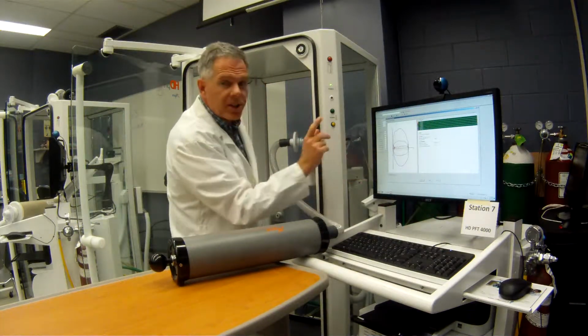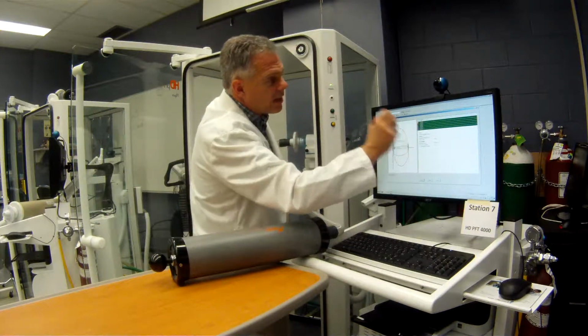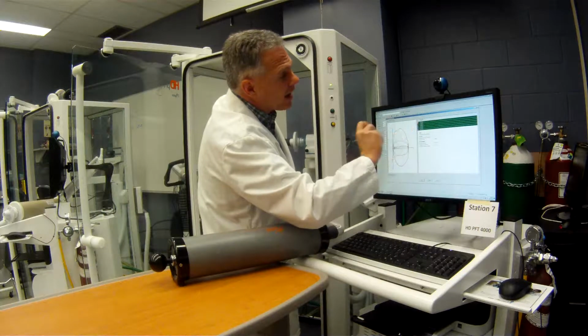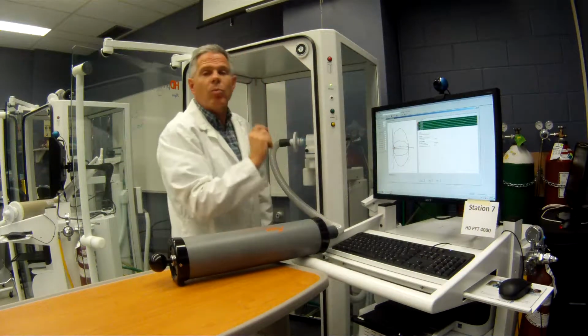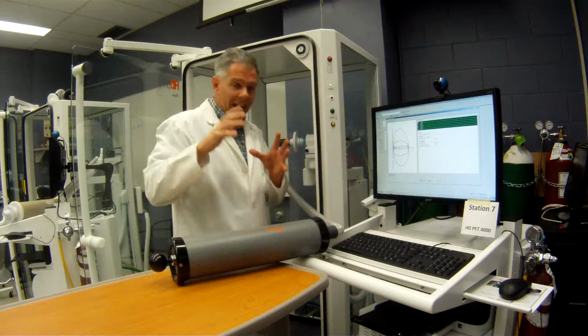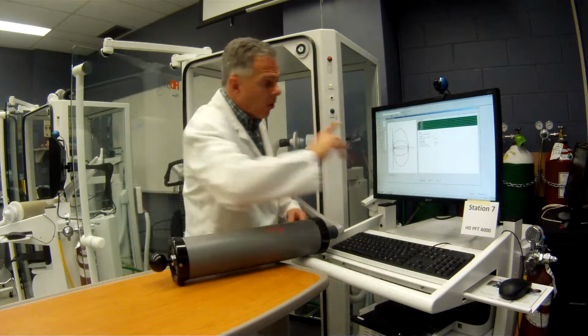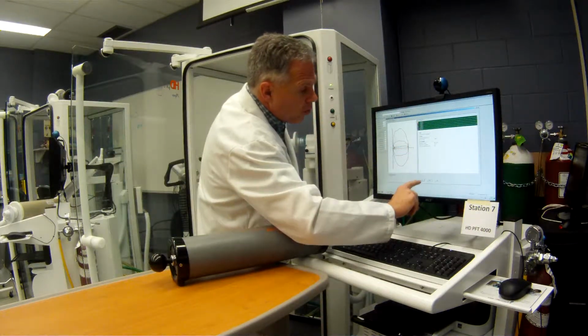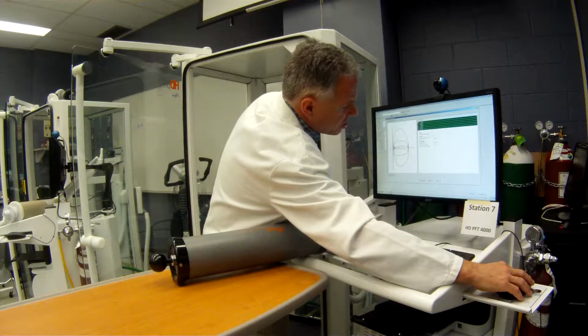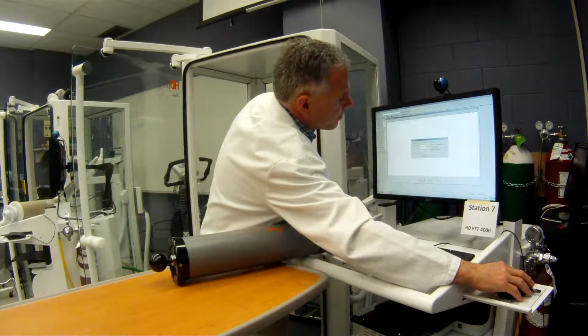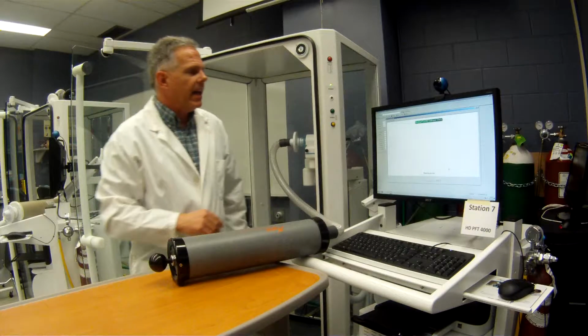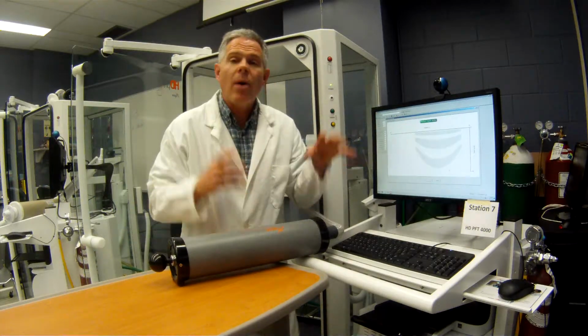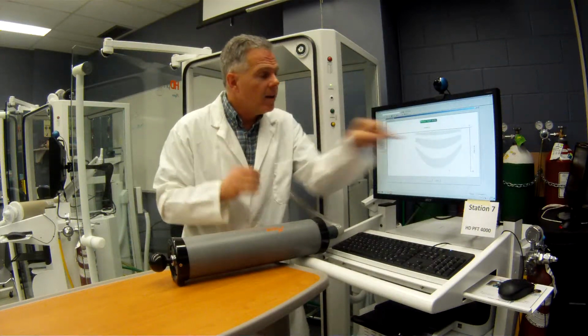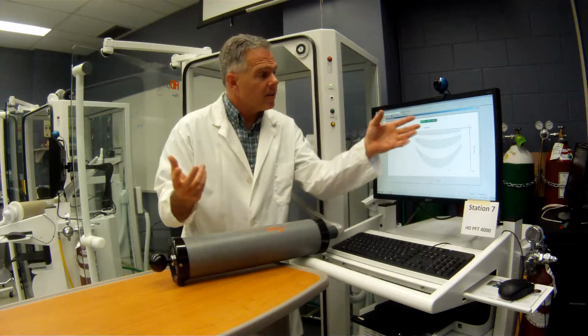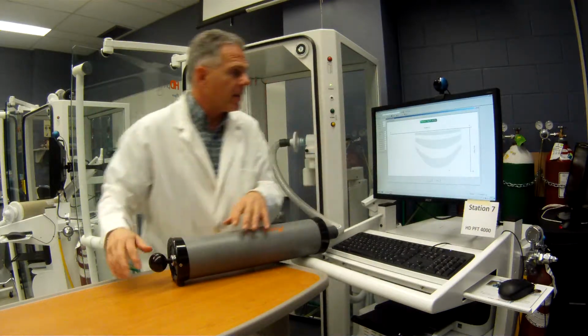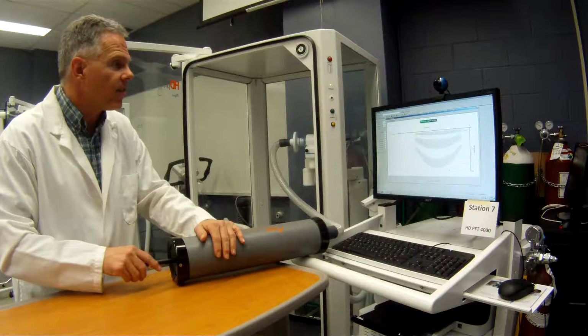We've done our calibration. You can see here everything's in the green, and right now we've only got an error of about less than 1 liter per second. So that meets our ATS criteria. So we're going to now do a check. Now in the check, it looks very similar. Got the same syringe, and it's going to tell us now to do a check. Now make sure we're checking that. It's a very similar procedure, but now we're checking it instead of calibrating it. So I'll do the same kind of things.